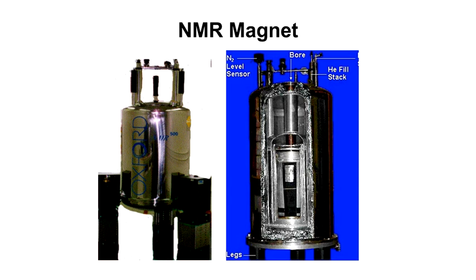The magnet is made up of niobium tin alloy. It's wrapped around to essentially create an electromagnet, which is charged just once. And then it's kept in very cold conditions, about 4 degrees Kelvin, so it stays superconducting.